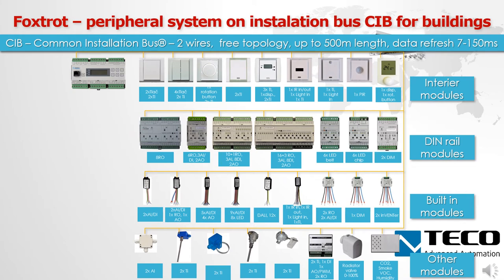Now we can speak about peripheral modules on CIB, the common installation bus for buildings. The bus has a free topology; we can go up to 500 meters distance from the central module. We can create free branches, no termination is needed, and data refresh is from 7 to 150 milliseconds according to the number of modules on the bus, so maximum, even fully loaded, is 150 milliseconds.